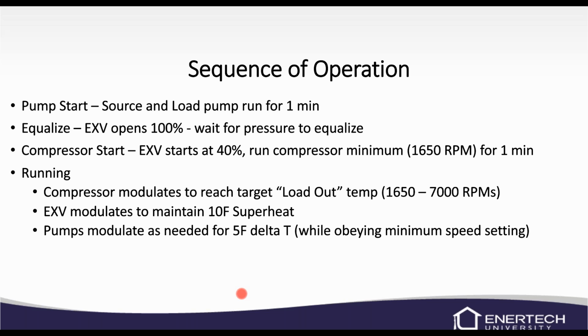It's going to try to always maintain that minimum speed setting. So if it's running at a minimum pump speed of 25%, and that delta T puts it at 4 degrees, it's not going to slow the pump down anymore, because it can't; your lowest setting is 25. So it'll just putt along there.